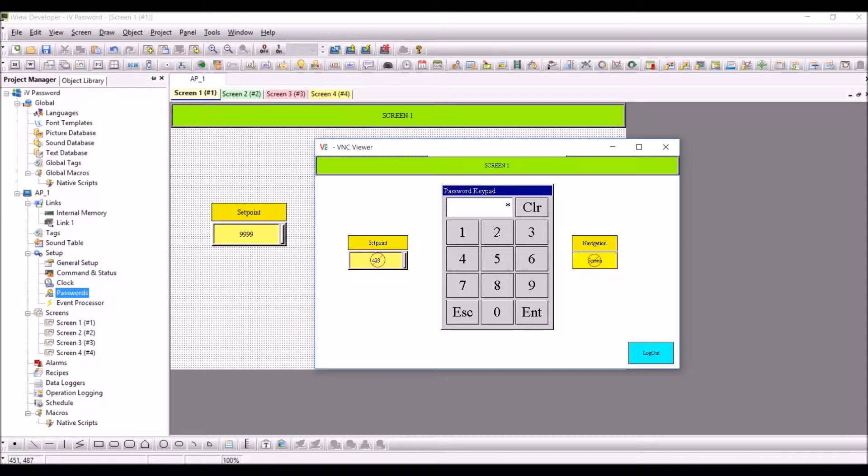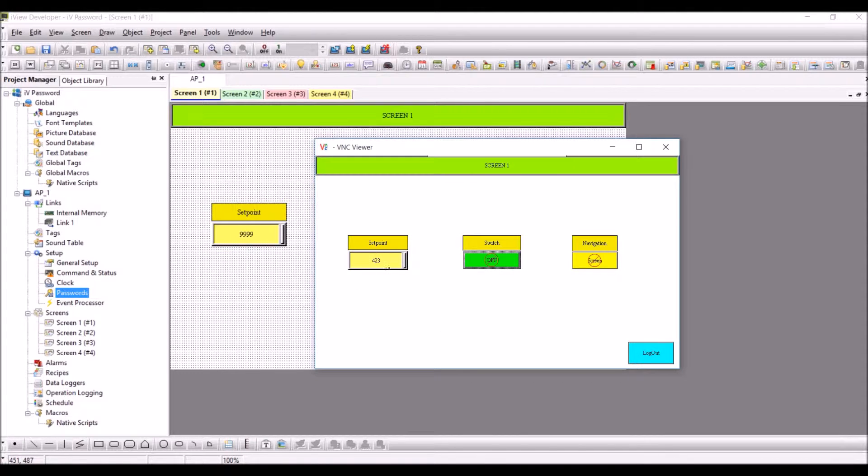I enter the correct password, one two three four, and enter. You can see that the disable button sign has been taken away and now it is up for any changes. I have entered one two three four, and you can see the setpoint has taken the correct value. You can see four five six, so it has taken the correct value.